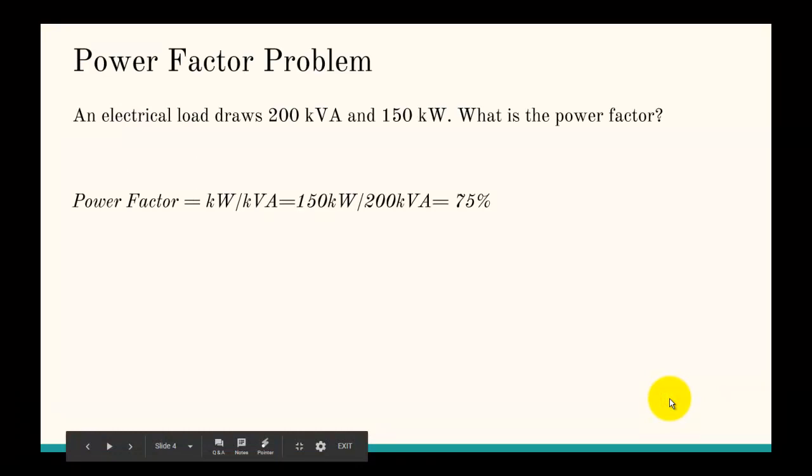So, this is a very simple power factor problem. An electrical load draws 200 kVA and 150 kW. What's the power factor? So, for the definition of power factor, it equals the kW over the kVA. So in this case, we get 75%.